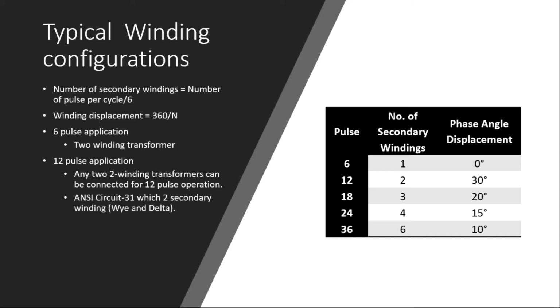Another industrial method for the 12 pulse is the extended delta configuration, but we mostly prefer to go for the 12 pulse in the delta and Y configuration, which is ANSI circuit 31. And the coupling configuration plays some importance when it comes to short circuit requirement and loss requirement. Normally that is specified in the specification.